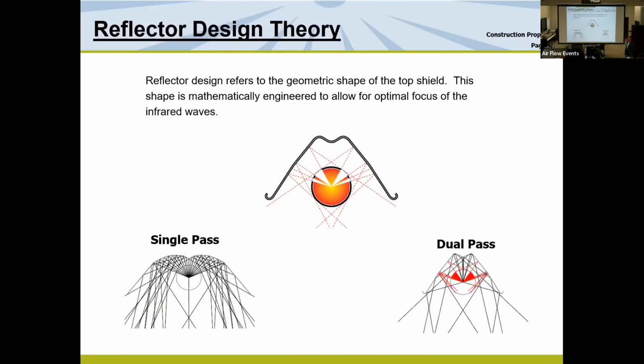There's a lot of discussion in our industry about reflector geometry. Okay, that top big depiction right there is our typical design reflector. The white gaps on that tube are our reverberate concept. We try to bounce some of the energy off the reflector and back into the tube. And by doing that, we raise the tube temperature by about 40 degrees. So from roughly 1,000 degrees up to 1,040. But if you take 40 to the 4th power, you get a much more effective radiant heat output than you would if you had a cooler tube.